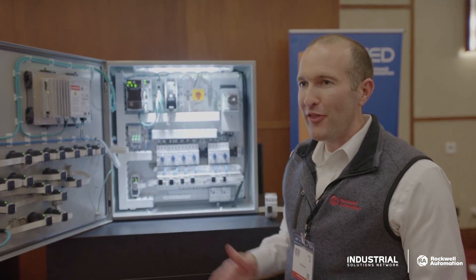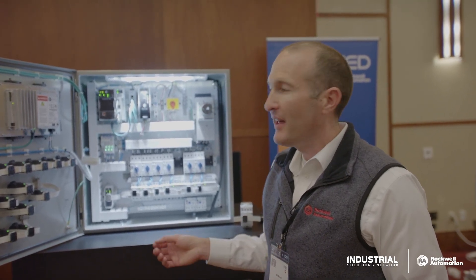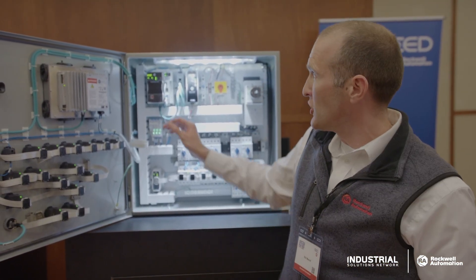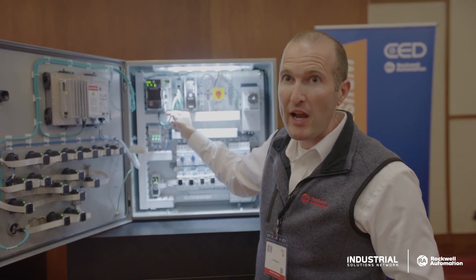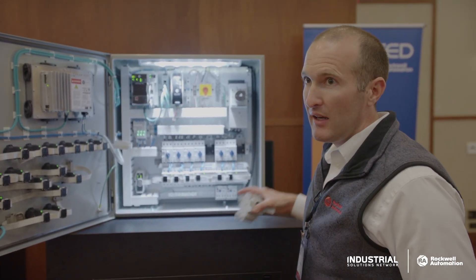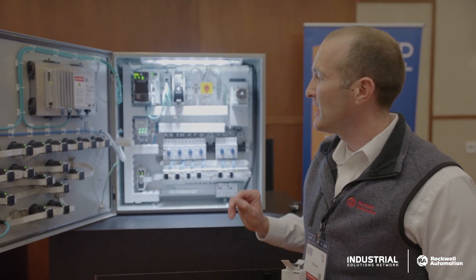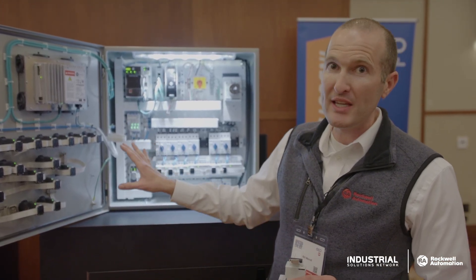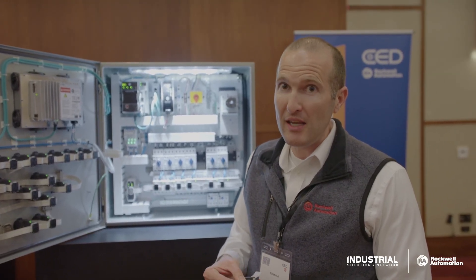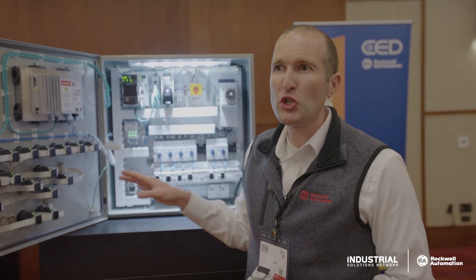Technology continues to evolve. Ethernet IP has been around for a while, but one of the new technologies that has come out recently is called single pair Ethernet. Your typical traditional RJ45 style Ethernet uses eight wires. Single pair Ethernet actually only uses two conductors. We embed that into a ribbon cable along with some power wiring and node addressing, which allows us to do this inside a panel and get true Ethernet IP communication over this flat media to these constrained devices.